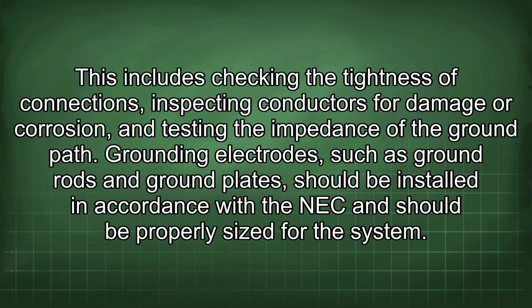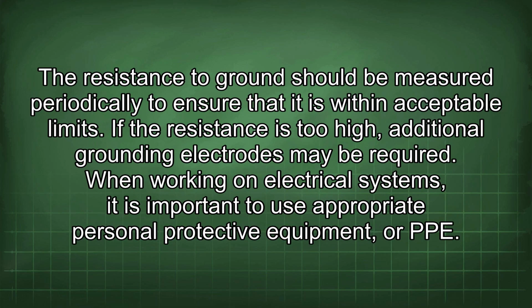Grounding electrodes, such as ground rods and ground plates, should be installed in accordance with the NEC and should be properly sized for the system. The resistance to ground should be measured periodically to ensure that it is within acceptable limits. If the resistance is too high, additional grounding electrodes may be required.